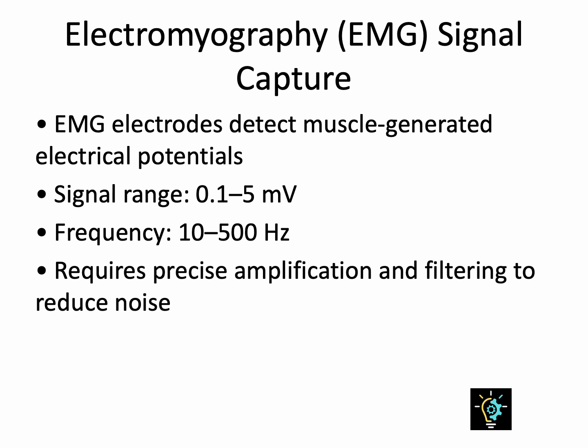Electromyography is the interface between biology and electronics. EMG sensors detect the electrical potentials that occur when muscles contract. These signals are tiny, often less than a few microvolts, and can easily be masked by noise from nearby electronics or motion. Engineers use high input impedance amplifiers and bandpass filters to isolate the desired frequency range between 10 and 500 Hz. Once clean, the signal is digitized for processing.